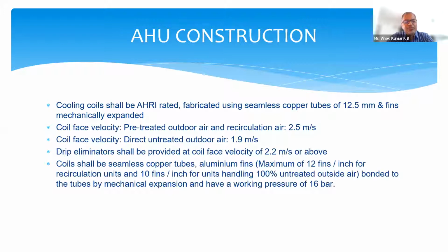Now, when I said air is passing through the coil to cool, we have to maintain a kind of velocity. What is the velocity of air that you will maintain through the coil? You have to maintain up to a maximum of 2.2 meters per second of velocity. The air passes through the coil at a maximum of 2.2 or not more than 2.5 meters per second, because if the air goes at a higher velocity, it will carry water along with it. Now, where does the water come from? The water comes from the coil itself. How does the water come?